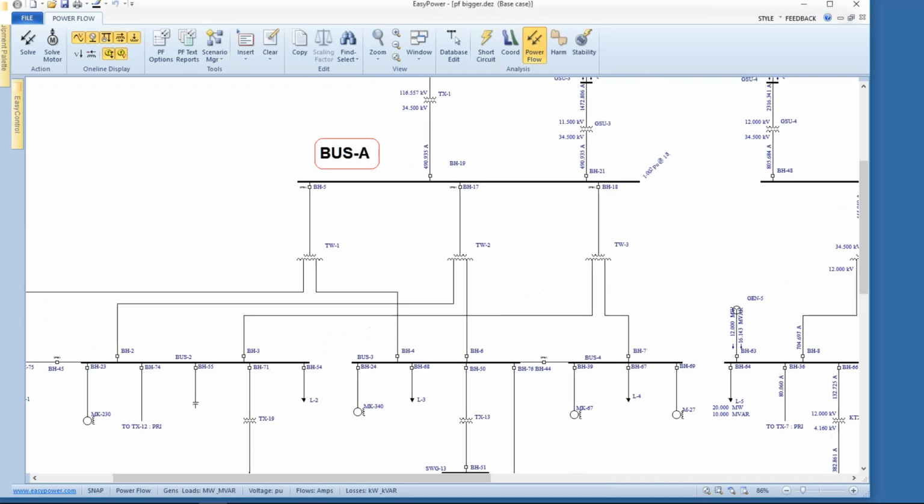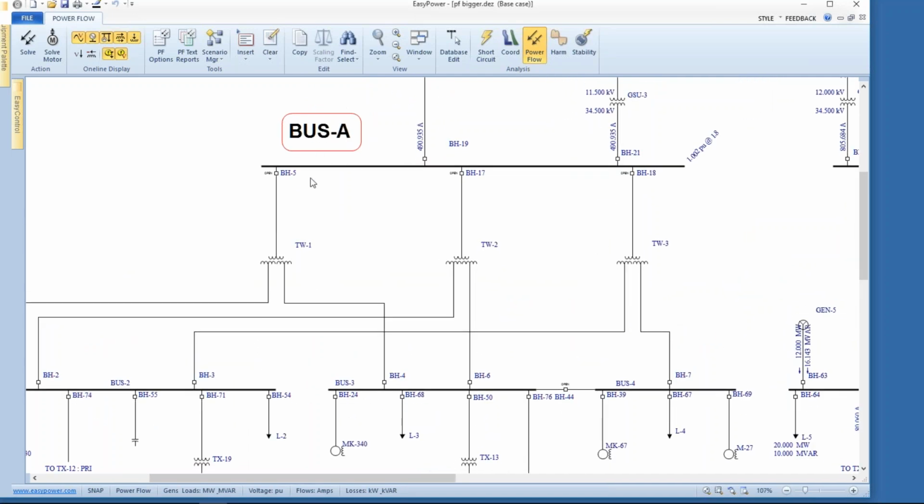You may have noticed when I started off that this breaker was open, and that's the error that I introduced to my system: with this breaker open I have a fair amount of overload induced that's not necessarily part of my circuit. So again, because that was introduced artificially, I'm going to go ahead and close each of these breakers.